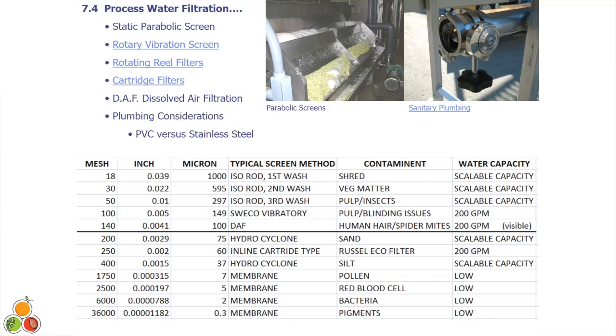This chart indicates that as you try to get down closer to 5 or 7 microns of filtration, with our environment's debris loading and water quality, it's going to get real expensive. So 200 gallon a minute RO systems, reverse osmosis systems, start at around the 750K range.